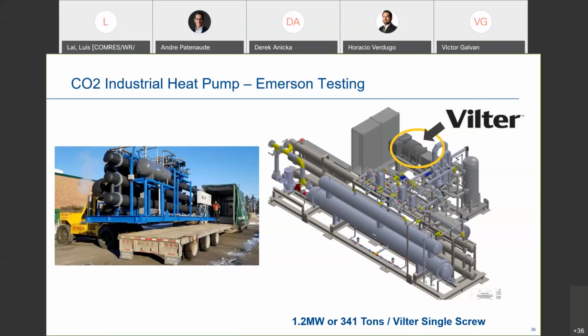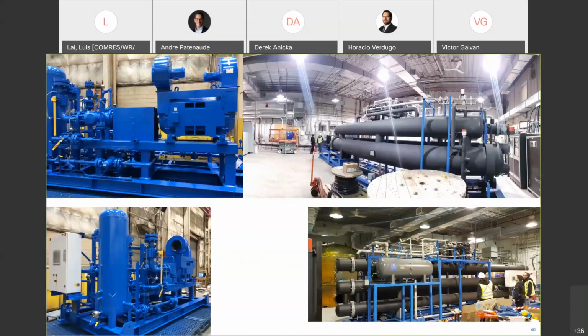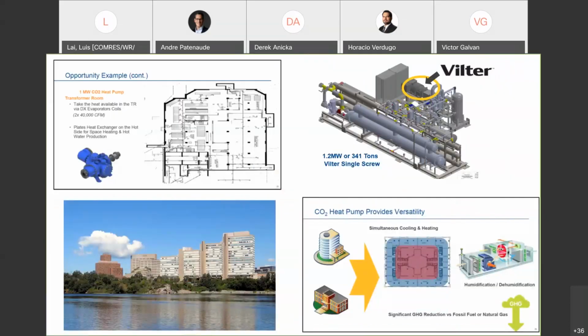You can see the unit on the left. That's the chiller component, the heat exchanger part. Vilter's built a skid pack with a screw on it. The equipment is on site right now. This utility really had to build a special floor and supports to handle this large weight. It's been delayed now because of the COVID situation. However, as soon as we can get back to operation, we'll start testing this heat pump application because there's a lot of interest in these large commercial buildings, especially the government-owned ones that have greenhouse gas reduction targets. So once this unit gets tested at the utility and it's validated, it already has a home. And once it's validated, there's a potential for 5 more within one building.